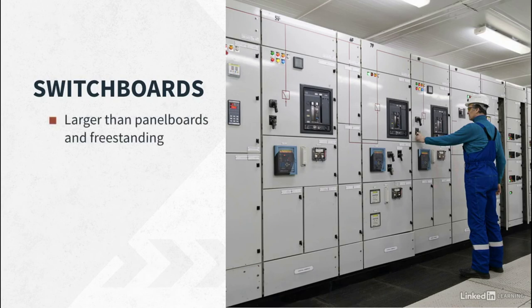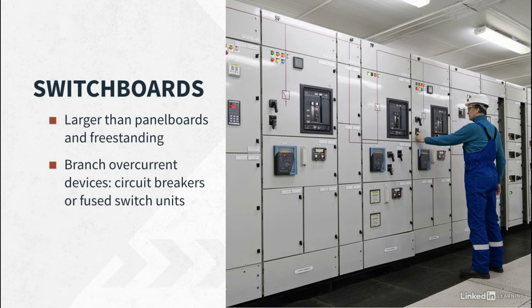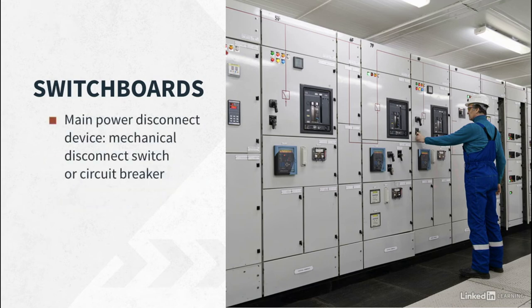Switchboards are larger than panelboards and sometimes freestanding. The branch overcurrent devices are either circuit breakers or switch units that have fuses inside of them. Switchboards may have a main device to disconnect the power, either a mechanical disconnect style switch or a main circuit breaker.